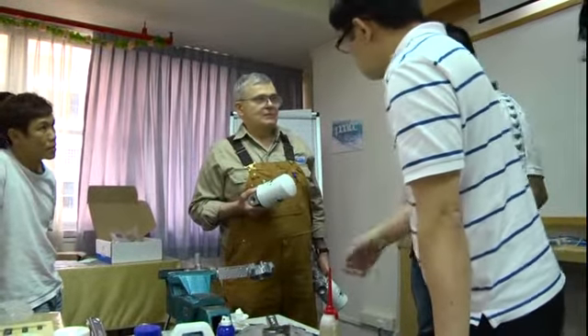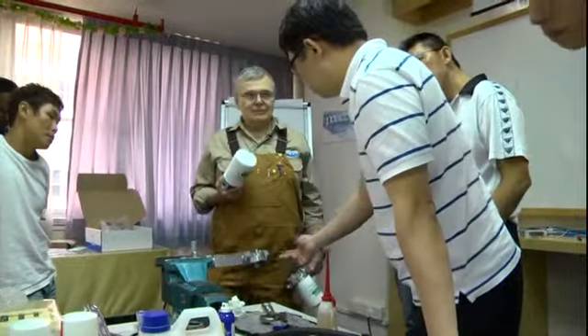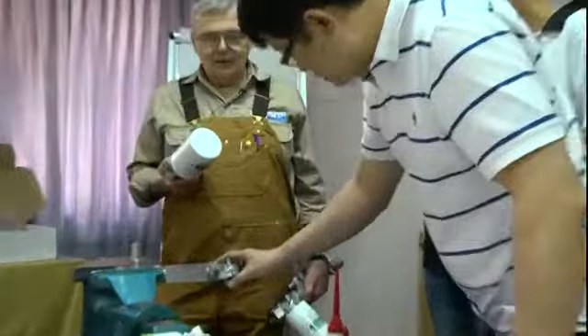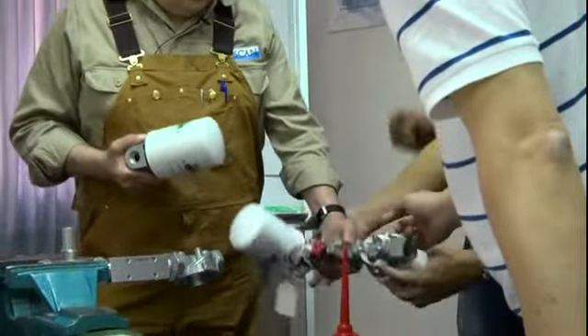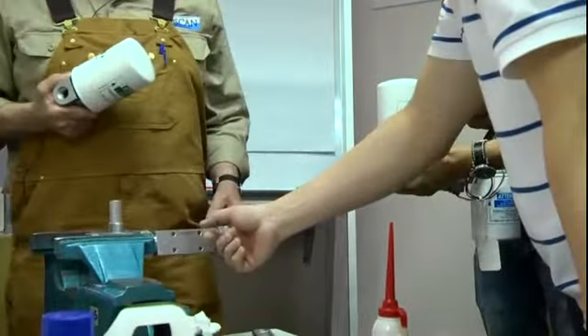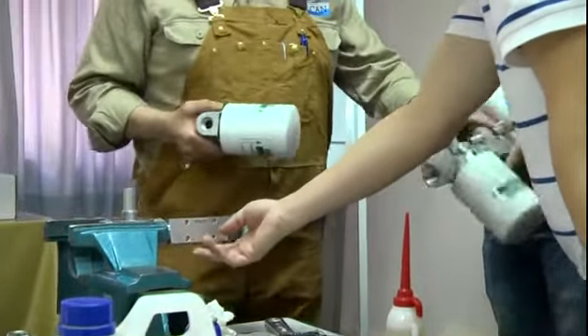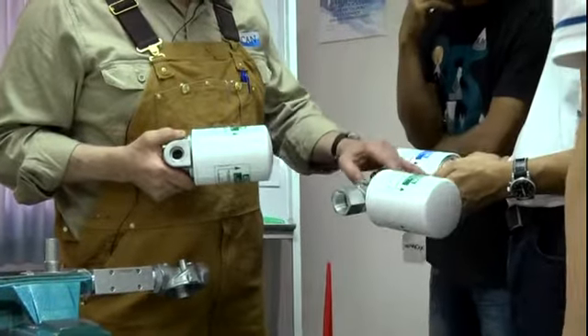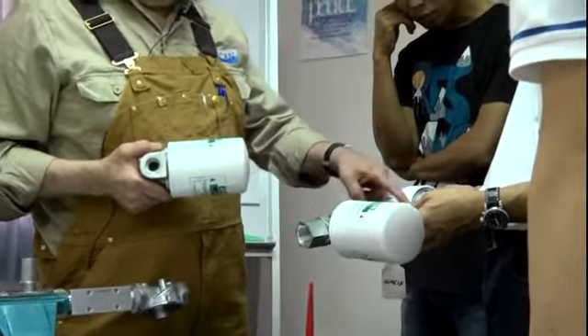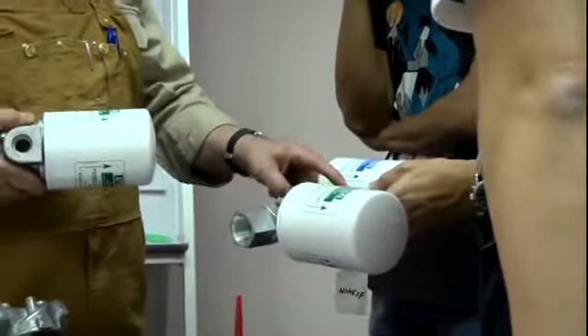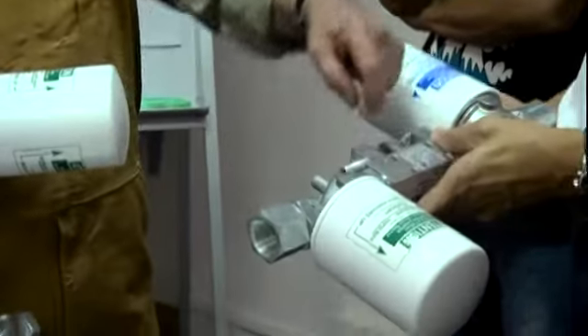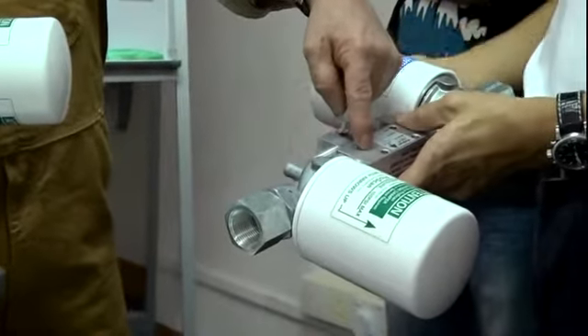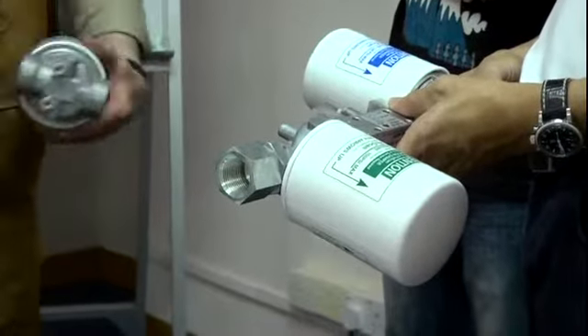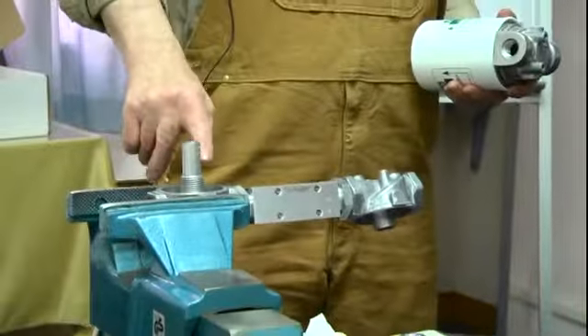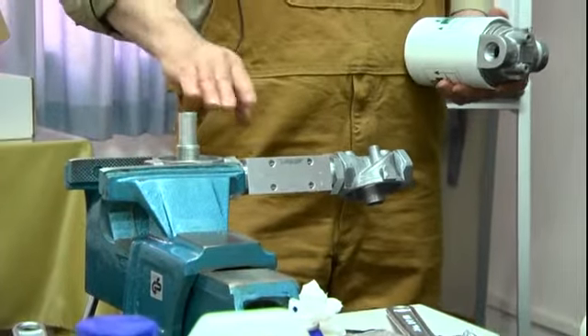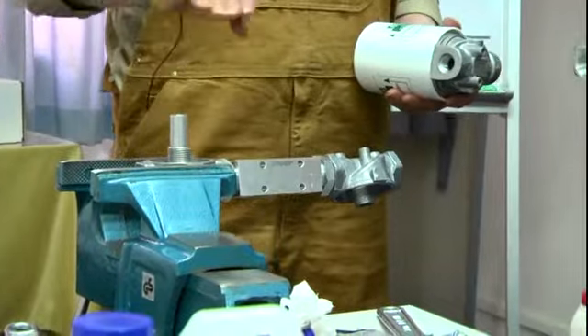That's a good thing to know. Sorry, when the fuel is going to this structure, it first goes through here, but the sensor is somewhere here. Right, the sensor is here. The majority of the flow goes through the block. Only some of the flow comes down into the sensor, spins the sensor, goes out the sensor, and then the two flows join at this point right here, and they all go through the pulsation damper. They come into the body of the damper until it fills up to the top of the standpipe, overflows the standpipe, then goes down and goes back to tank.